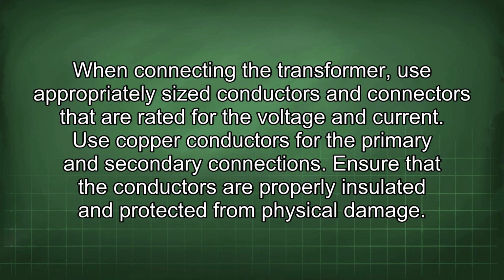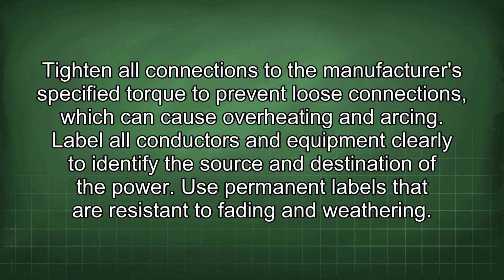Use copper conductors for the primary and secondary connections. Ensure that the conductors are properly insulated and protected from physical damage. Tighten all connections to the manufacturer's specified torque to prevent loose connections, which can cause overheating and arcing. Label all conductors and equipment clearly to identify the source and destination of the power.